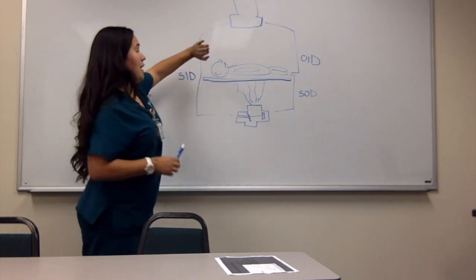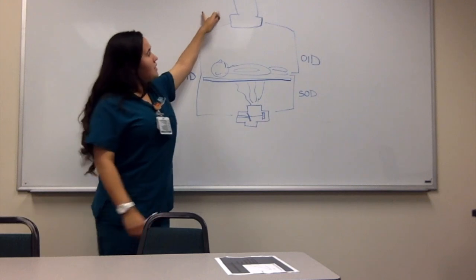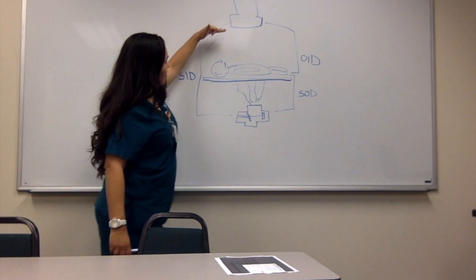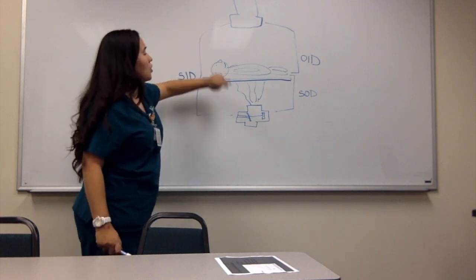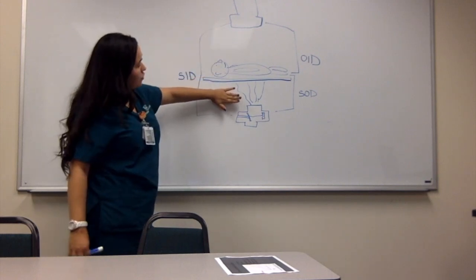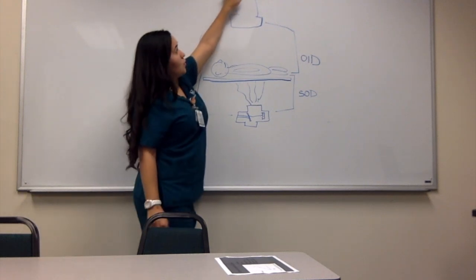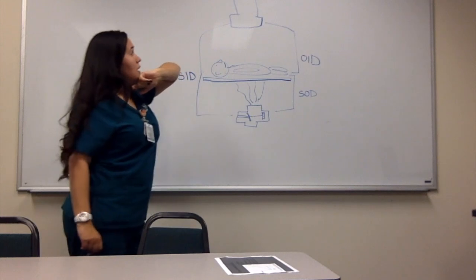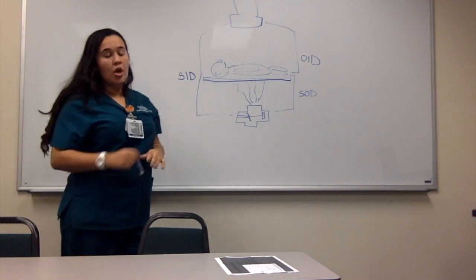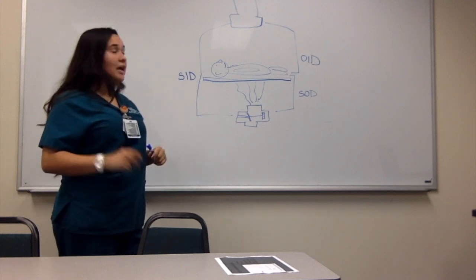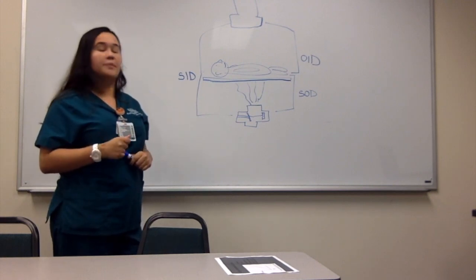The tube is at the bottom and the tower is at the top, and this has the image receptor. The closer the image receptor is to the patient, the quicker the x-ray photons reach the tower and it gets to the ABC, which is automatic brightness control, which is also kind of like an AEC chamber. And as soon as it reaches that, it shuts off the system.